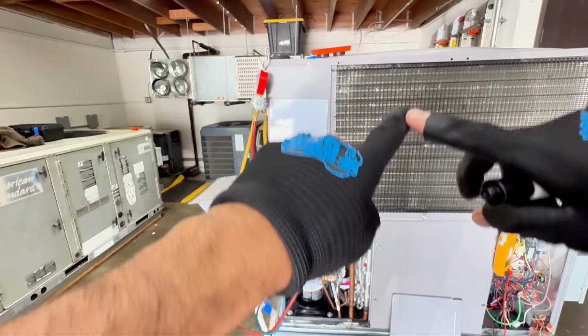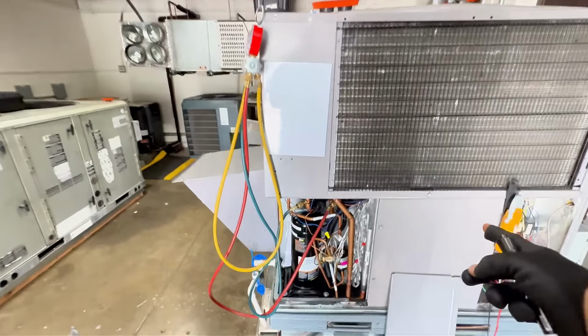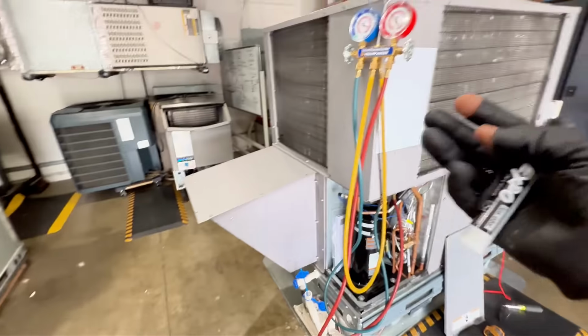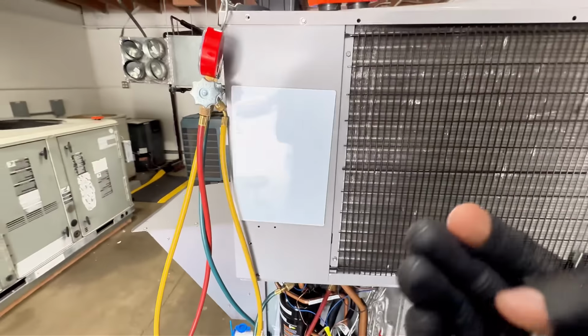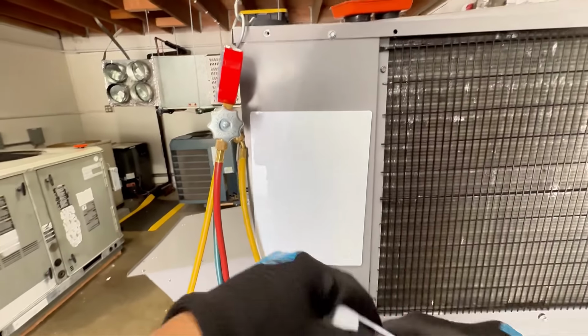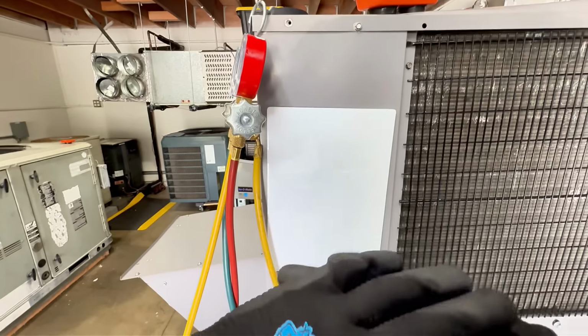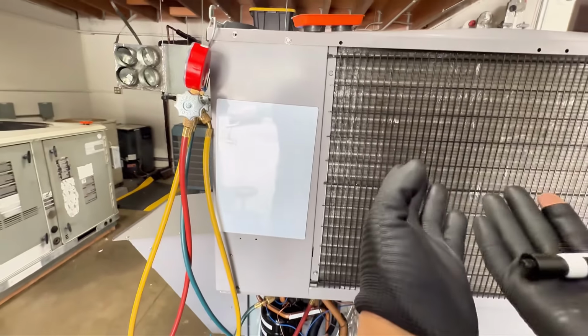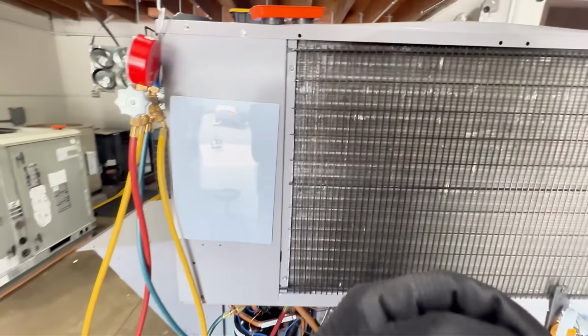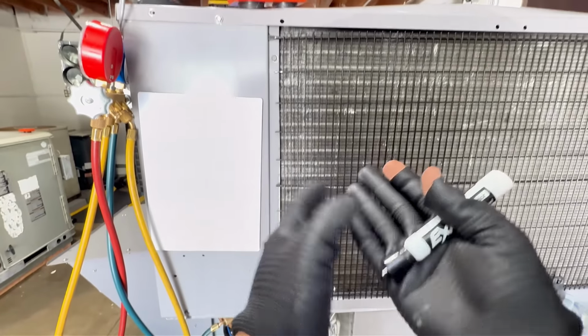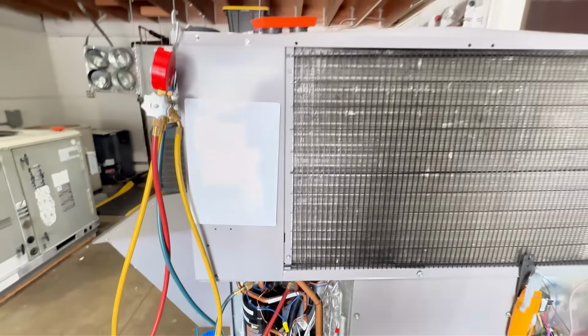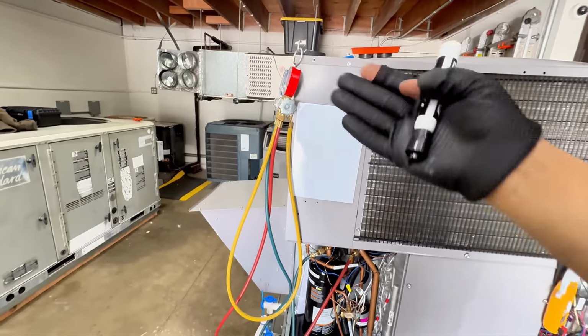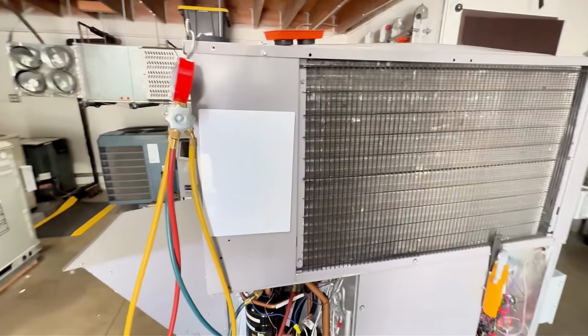Wait 10 minutes. Check airflow. Check that your filter is clean. You have good return air and supply air. But I'm going to show you, and this is, of course, with time, by just getting superheat and subcool, you'll know what's going on with the whole system without even checking airflow. Now, I'm not saying don't check airflow. When you're starting off, check airflow first, okay? Then check your pressures. But I'm going to show you by just looking at superheat, subcool, and my pressures if we have an airflow issue.